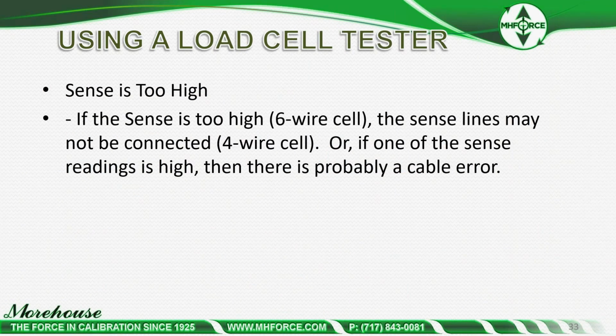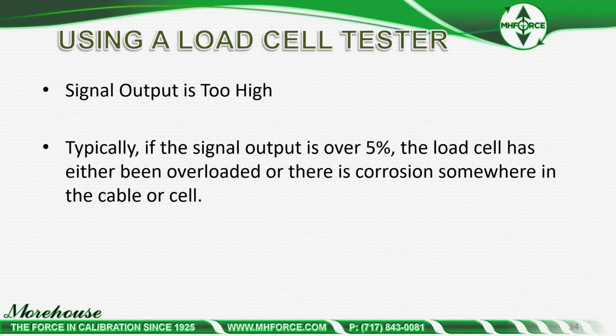If the sense is too high, you can get that warning, the sense lines may not be connected. Or if one of the sense line readings is high, then there's probably a cable error. Again, go back and troubleshoot the cable. Signal output is too high. Typically, if the signal output is over 5%, the load cell has either been overloaded or there is corrosion somewhere in the cable or cell. The ones that we see are always overloaded. So if you're in a rough production environment, you may deal with corrosion somewhere else in the cell.